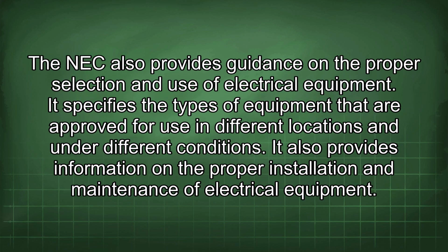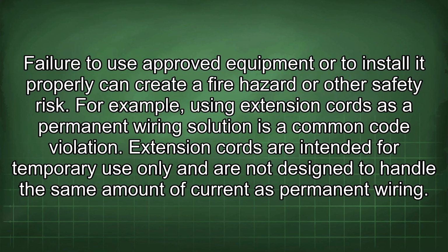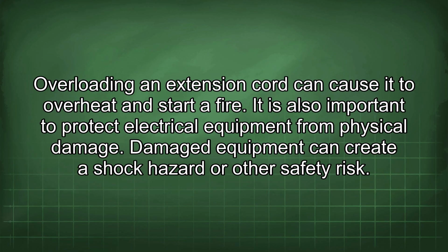The NEC also provides guidance on the proper selection and use of electrical equipment. It specifies the types of equipment that are approved for use in different locations and under different conditions. It also provides information on the proper installation and maintenance of electrical equipment. Failure to use approved equipment or to install it properly can create a fire hazard or other safety risk. For example, using extension cords as a permanent wiring solution is a common code violation. Extension cords are intended for temporary use only and are not designed to handle the same amount of current as permanent wiring. Overloading an extension cord can cause it to overheat and start a fire. It is also important to protect electrical equipment from physical damage.